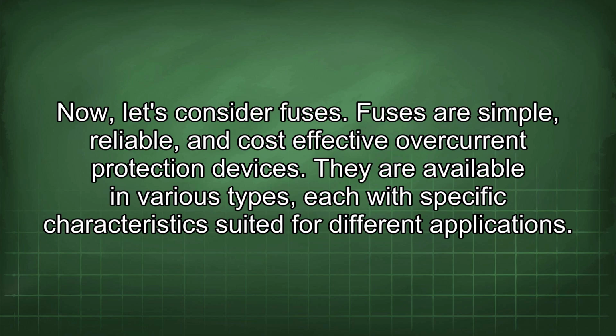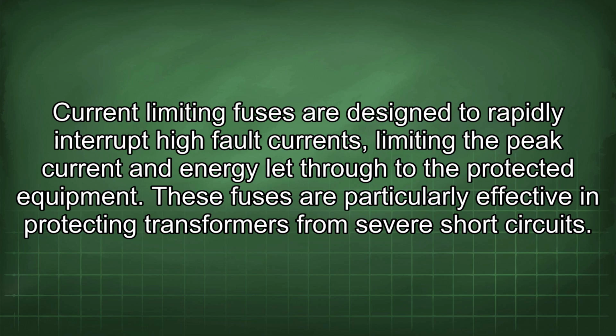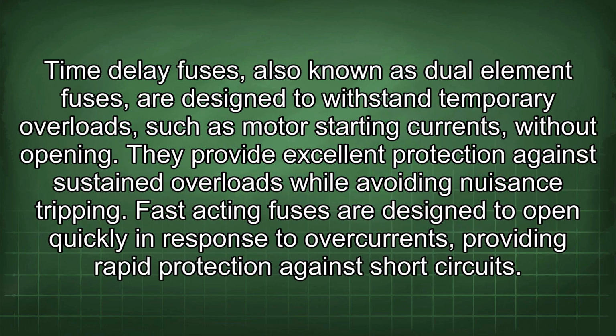Fuses are simple, reliable, and cost-effective overcurrent protection devices. They are available in various types, each with specific characteristics suited for different applications. Current-limiting fuses are designed to rapidly interrupt high fault currents, limiting the peak current and energy let through to the protected equipment. These fuses are particularly effective in protecting transformers from severe short circuits. Time delay fuses, also known as dual-element fuses, are designed to withstand temporary overloads, such as motor starting currents, without opening. They provide excellent protection against sustained overloads while avoiding nuisance tripping.